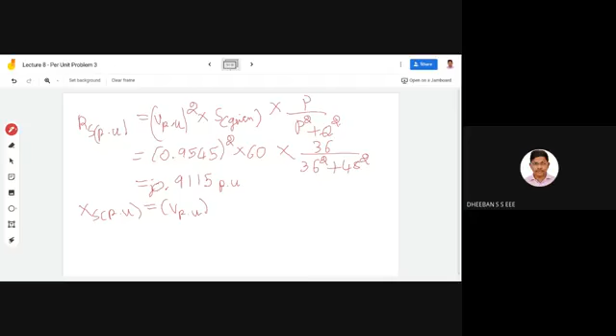Next we'll be finding XS per unit. The variation is in the reactive power, so it's V per unit the whole square into S given into Q by P square plus Q square. That gives 0.9545 the whole square into 60 into 48, divided by 36 square plus 48 square.